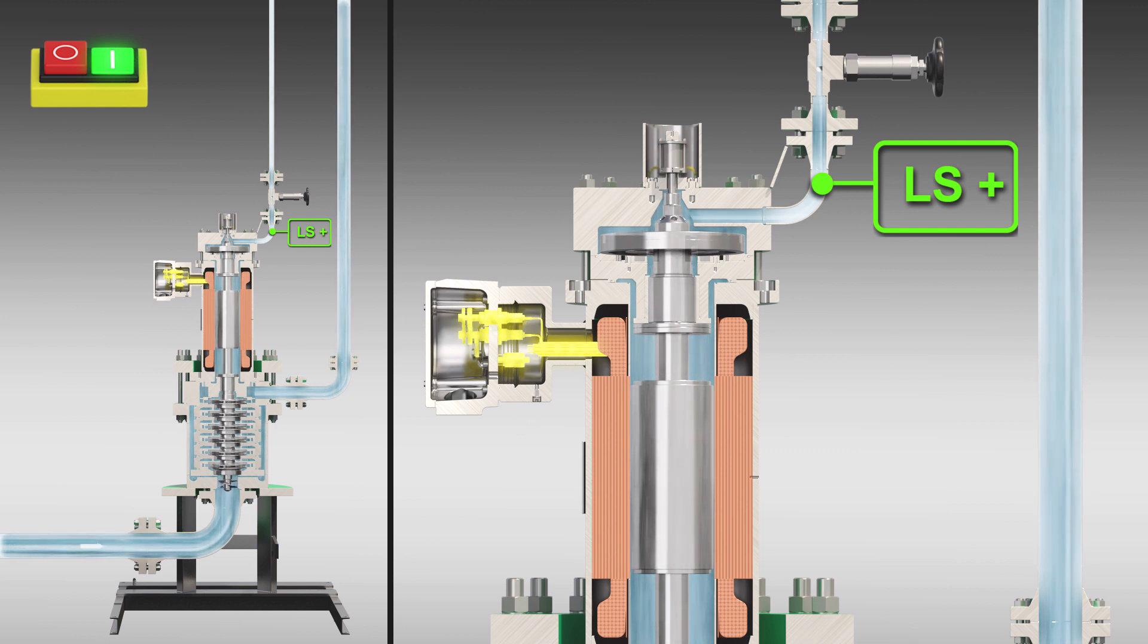Thanks to its design, the Hermetic canned motor pump is wear-free and requires no maintenance for continuous operation. Its multi-stage design offers better efficiency factors and lower NPSH values. An upstream inducer is installed to further reduce the pump's NPSH values.